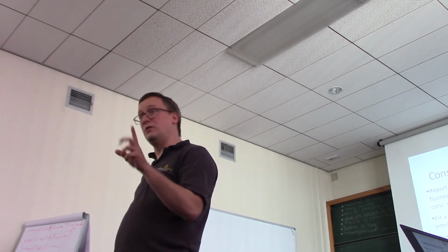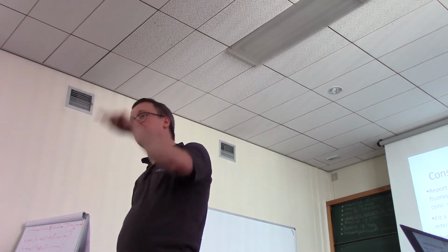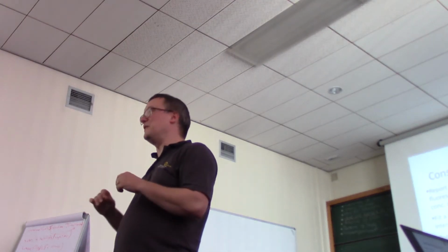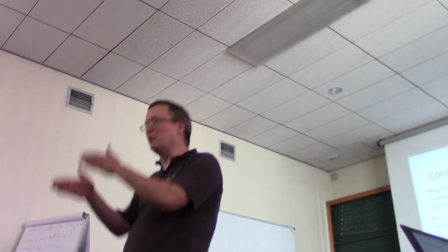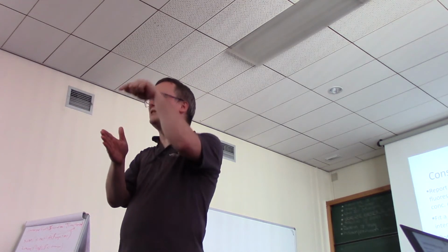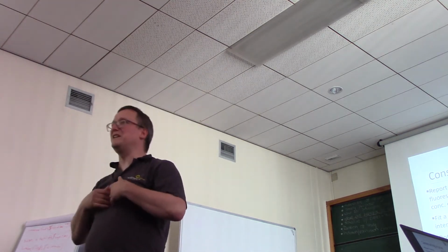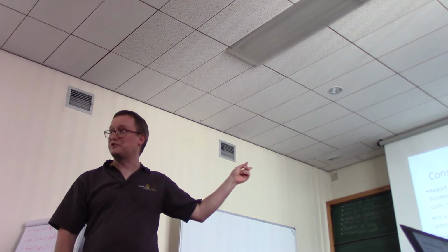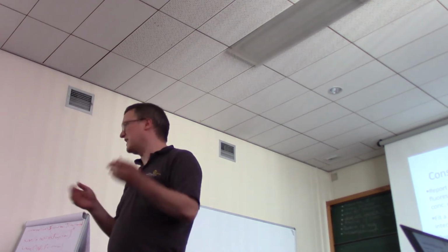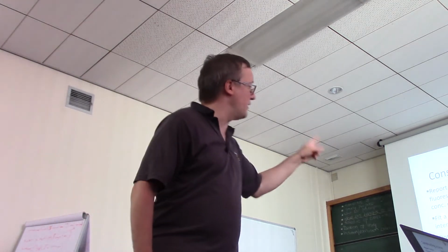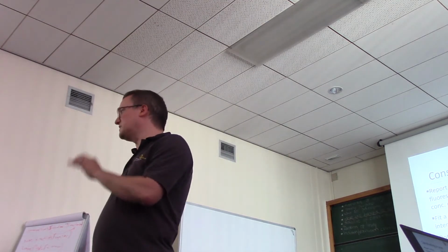You should, on every plate, check that the calibration curve actually overlays the points to which it was fit. If you see, for example, that you put a greater concentration of analyte in, but the intensity fell, you're in a world of hurt, right? So we want to be cognizant of the fact that these models are only as good as they're fit to the calibration points.